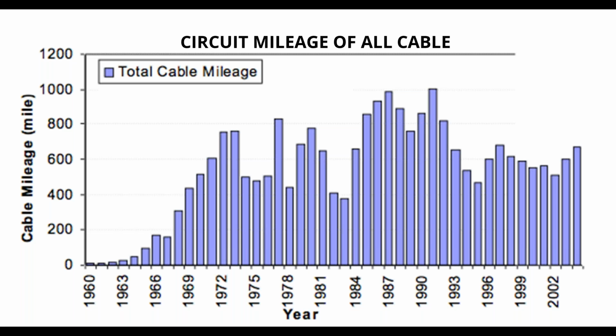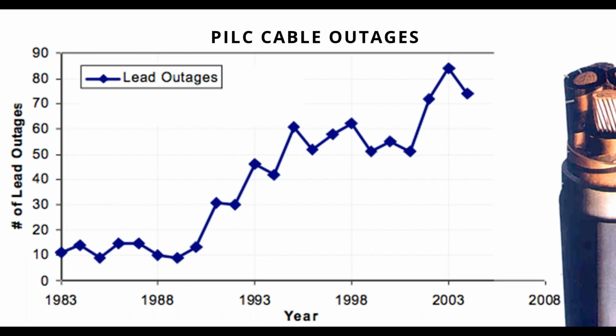And you can also look at these types of things to see, are there any sort of waves of really old stuff that are coming our way? If you start to see problems manifest themselves when cables are 35 years, do we have cables that are 30 years old that in 5 years are going to be a problem for us?